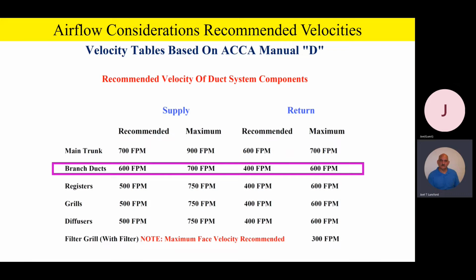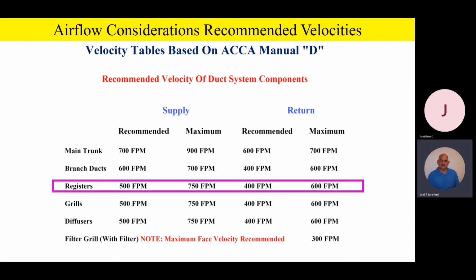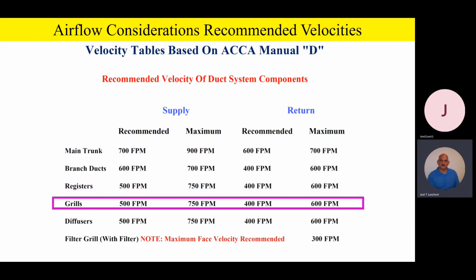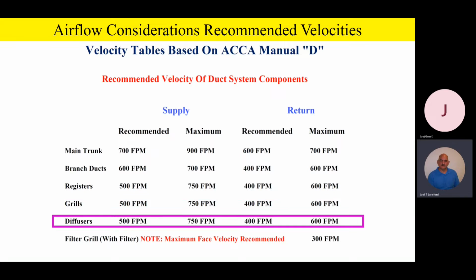Branch ducts, they specifically address at about 600 feet per minute recommended on supply, and about 400 for return. Registers and grills, 500 feet a minute on the supply, 400 on return. Diffusers are about the same. And this is a big one. This is really, really important.